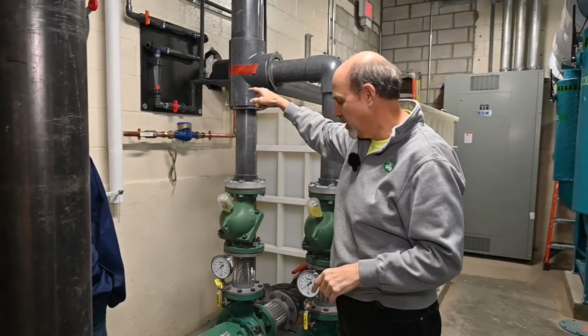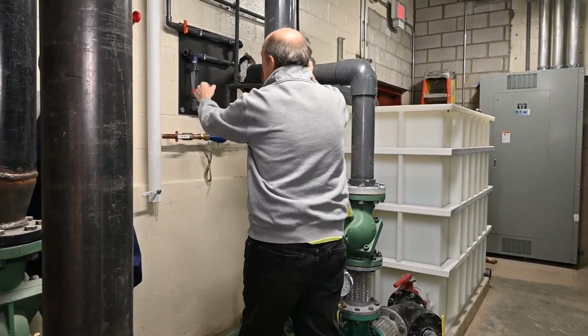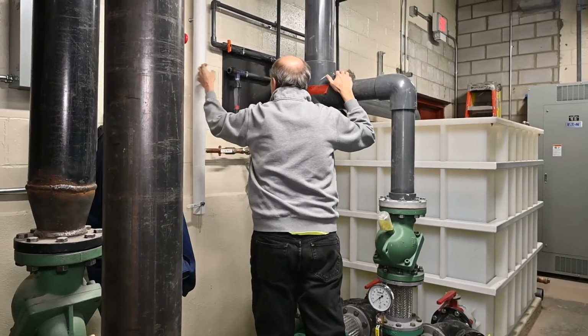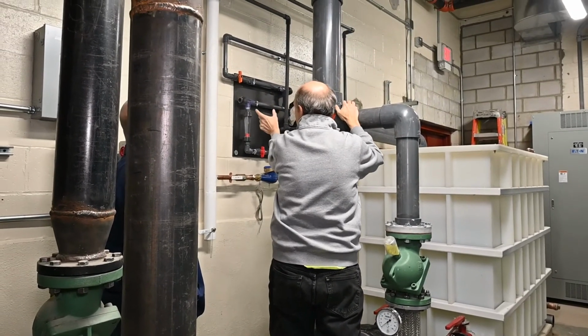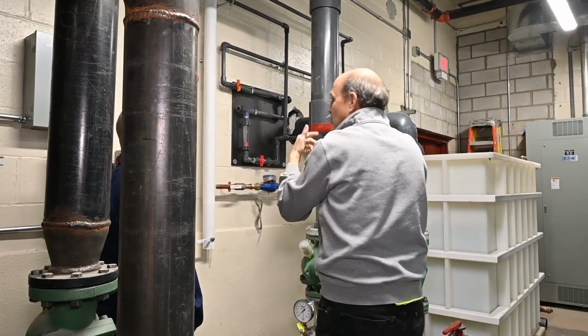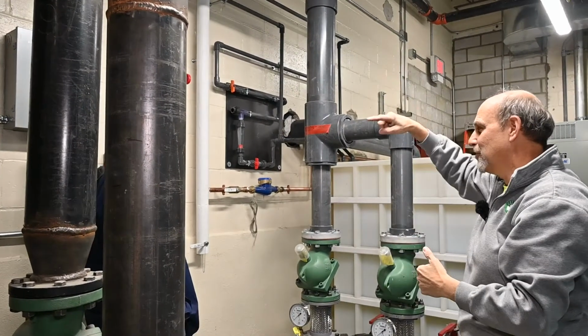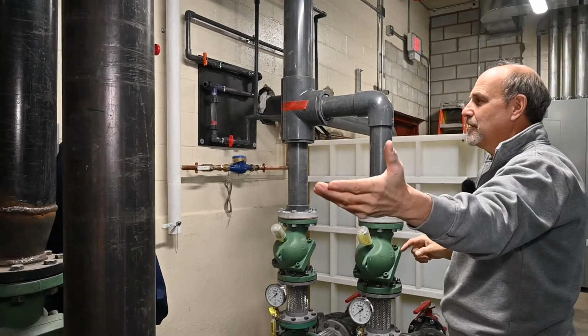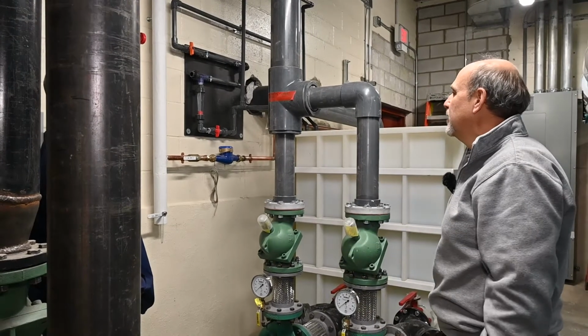But this is a coupon rack, and essentially what that technician does is he'll undo this and pull this out, same one over there, and there's an assembly in there that he can test as to what the corrosion level is of the cooling tower water that's through it, and he'll adjust the chemicals accordingly as well.